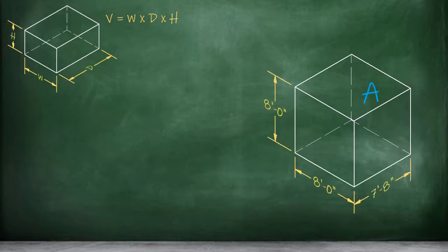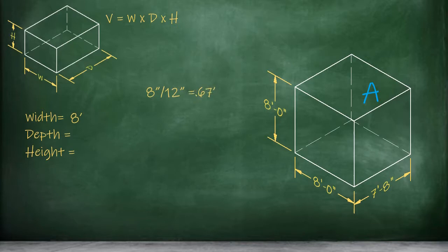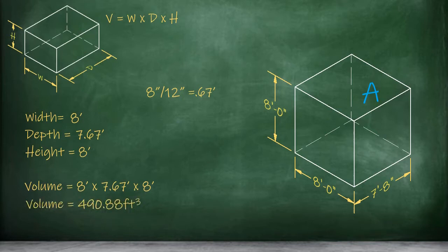Let's tackle space A first. To find the volume, we need to use the dimensions for width, depth, and height. Our width dimension is 8 feet, so no trouble there. Our depth dimension is 7 feet 8 inches, so we'll need to convert this into decimal feet before we can use the measurement in our formula. 8 inches divided by 12 inches equals 0.67 feet. When we add this back together with the 7 whole feet, we get a depth dimension of 7.67 feet. And our height dimension is also 8 feet, so no need to convert anything here. 8 feet times 7.67 feet times 8 feet equals a volume of 490.88 cubic feet for part A of our space.